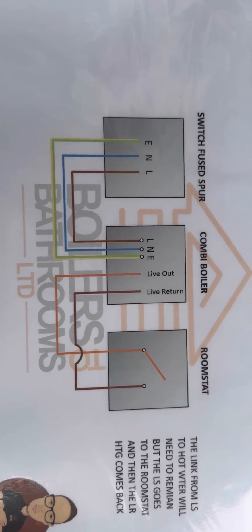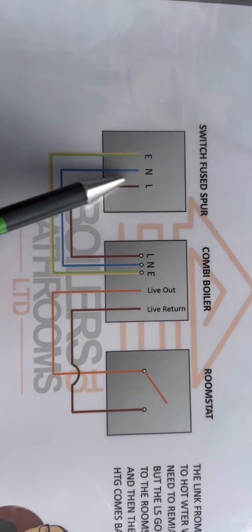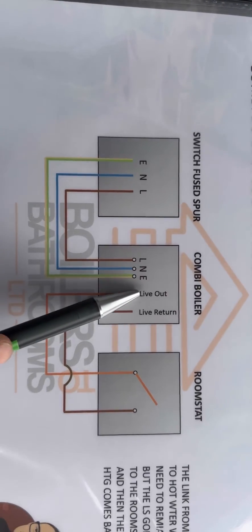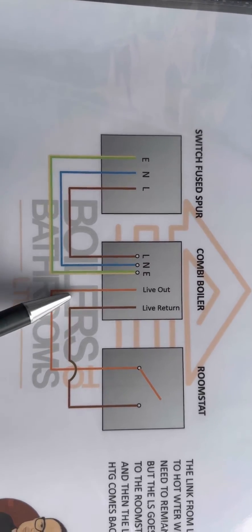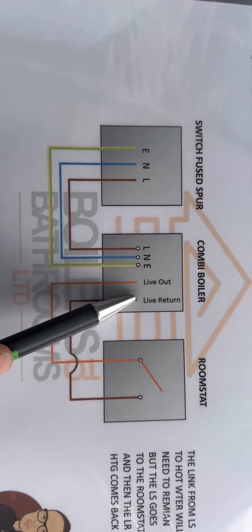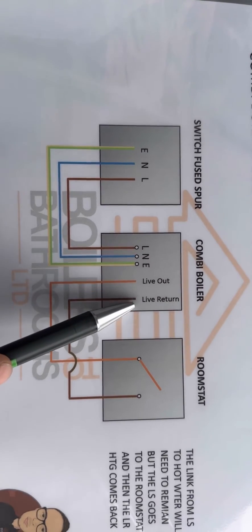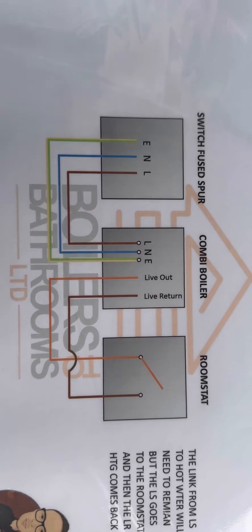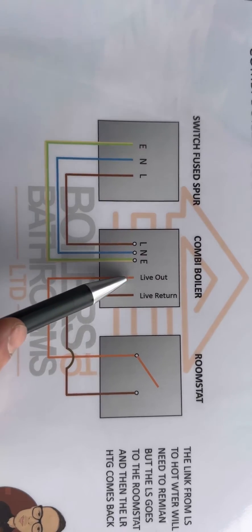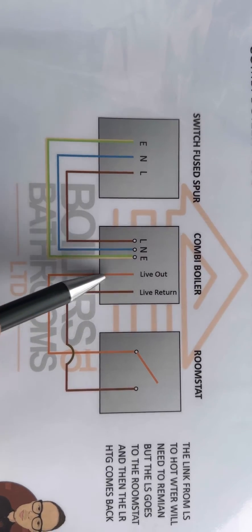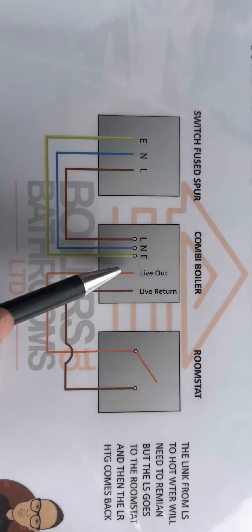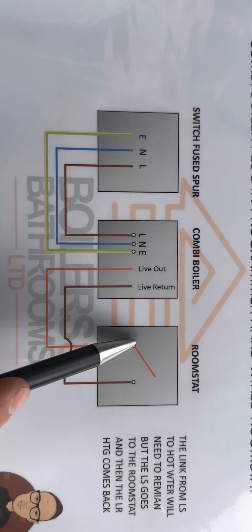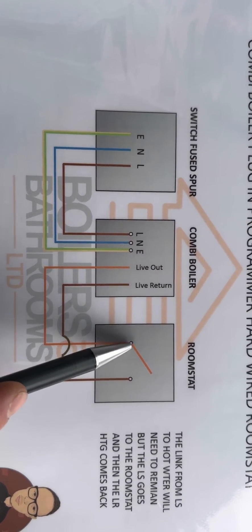This is basically what we just had in that scenario. It's a switched fused spur - live, neutral, earth goes to the boiler, and then you've got a live out which is LS, and a live return which is LR. So when we were checking for 240 on LS, we were checking here, and that was sending it out - we got that.